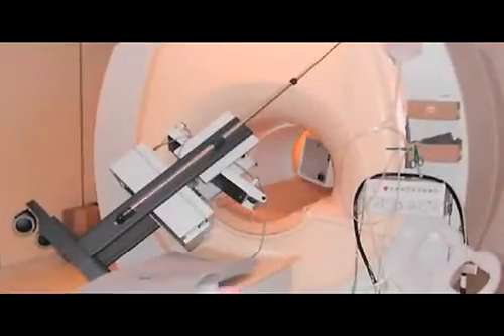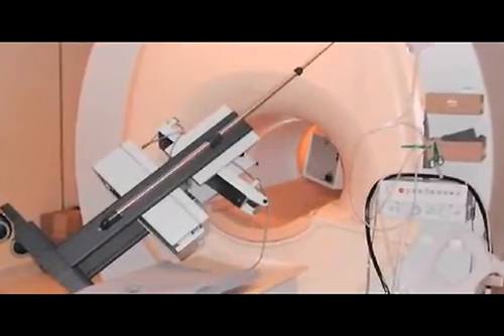The Joint Commission Sentinel Event Alert Number 38 states that injury or complication related to equipment or device malfunction or failure caused by the magnetic fields are among the most common sources of patient injuries in the MRI environment. The electromagnetic fields used for MRI include a powerful static magnetic field, rapidly changing magnetic fields, and RF pulses. Each of these electromagnetic fields can produce serious hazards with monitoring equipment.